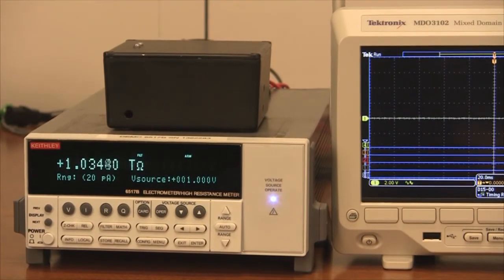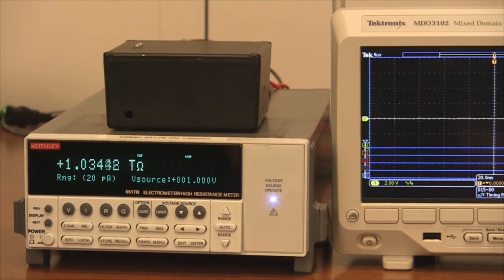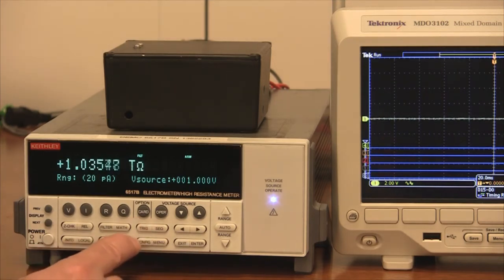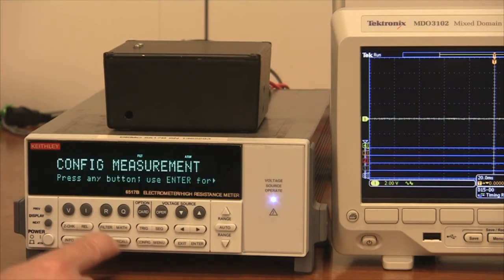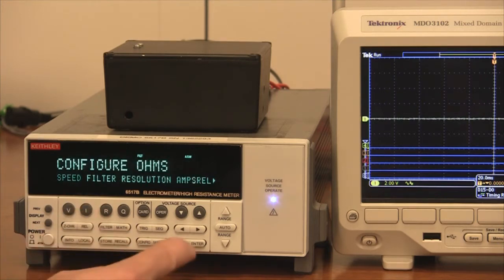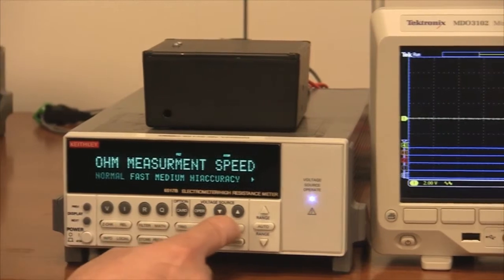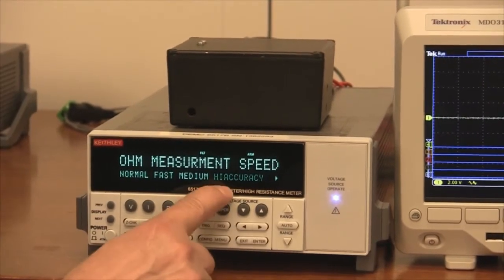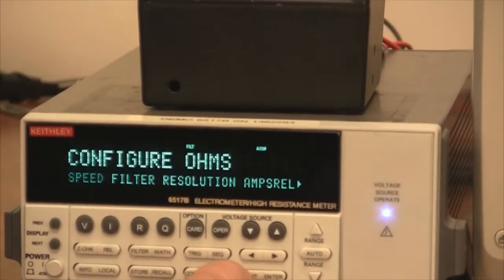This is in default condition, which means the A to D converter is set to 1 PLC. That's power line cycles. That's the time the A to D converter looks at the input signal. Well, we have control over that. We can make this a little better. So if we go to configure, resistance, speed, go to high accuracy, enter, exit.